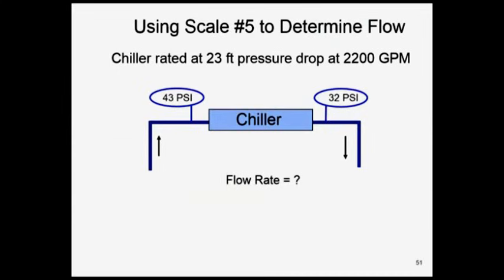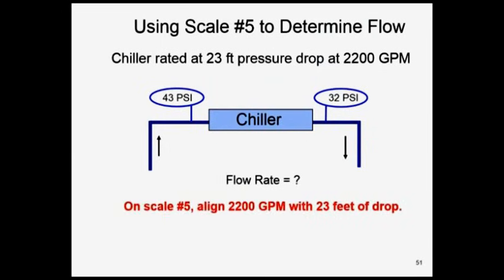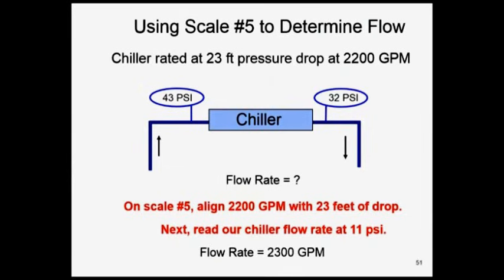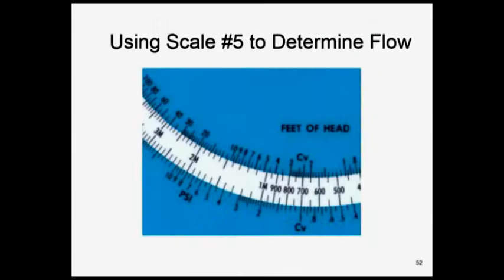Can we not go to scale 5 of the system sizer and come up with GPM now? Let's try it. So what do we know? We know it's 10 pounds of drop at 23 feet at 2,200 GPM. We know the pressure drop's 11 pounds. So on scale 5, you can do it on your little Android or Apple versions, or on the hand wheel, which is the old-fashioned way of doing it. Let's just show you a picture and see what we get. We can set it up at 2,200 GPM at 23 feet or 10 pounds, and we go to the 11-pound reading and read our flow rate. And what you will see is 2,300 GPM.